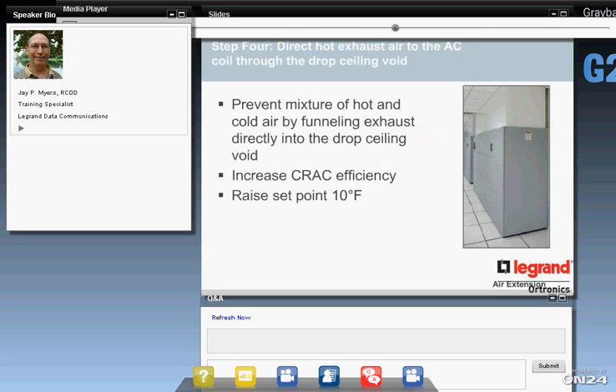The intake for most CRAC units is about 6 feet up off the floor, but you can tell if you just stand on a chair, stick your hand up near the ceiling, it's a lot hotter up higher. So if we can extend that intake up into the false ceiling, we can make sure that we get the hottest possible air back to our CRAC units. If you don't have a drop ceiling, even just extending that up 4 or 5 feet, the air stratifies pretty well. And if you can get that up where the air is hotter, it'll increase the efficiency of your units.